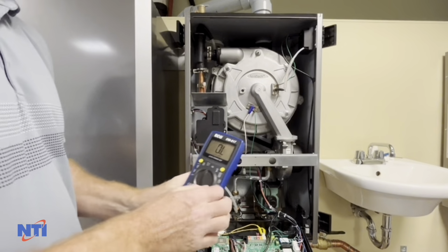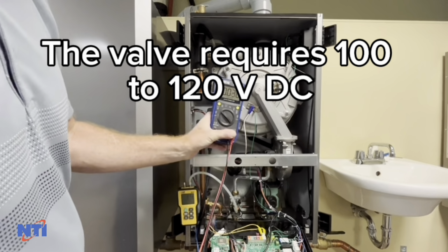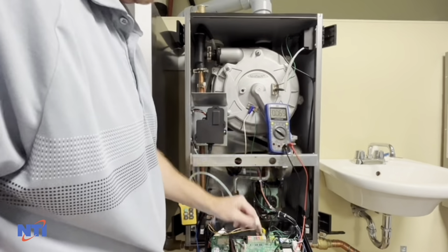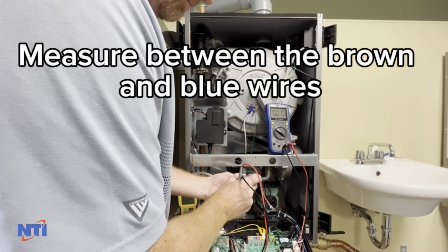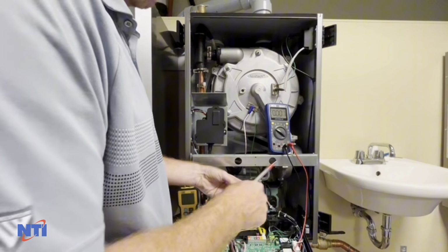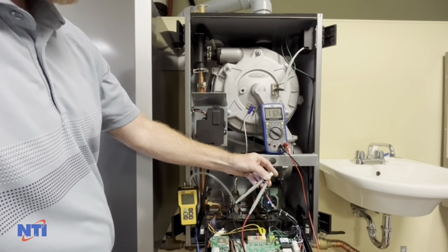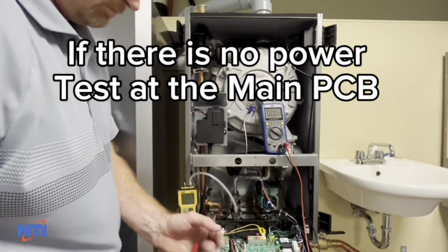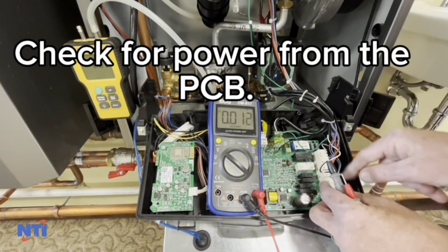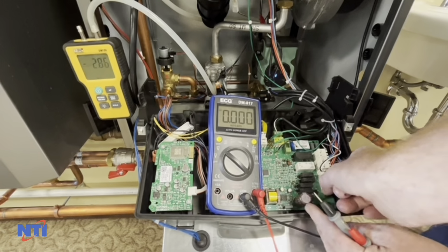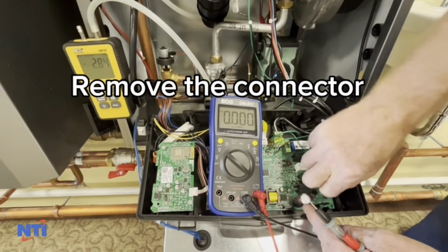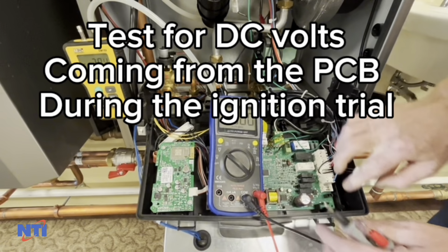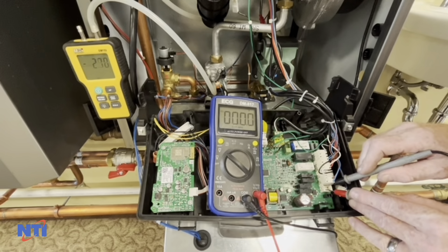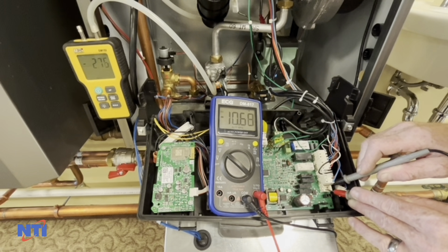If you do not see a pressure drop after multiple ignition attempts, test for 120 volt DC power to the gas valve. Remove the harness from the valve. Testing across the brown and blue wires, look for 120 volts DC for 3 to 5 seconds during each ignition attempt. Trace these wires back to the main PCB and test at the PCB if no power is present at the gas valve. Remove the connector, touch the meter leads to the 2 pins on the main PCB during the ignition trial. Reset any error codes to ensure the boiler is attempting ignition when doing this procedure.